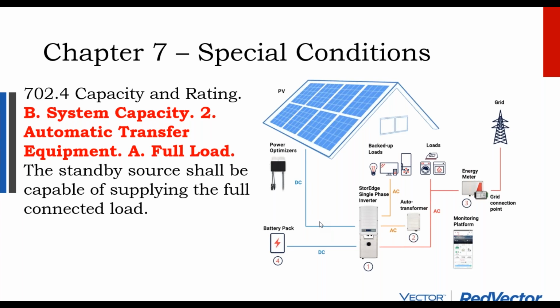Your systems would have to be very large and very expensive to get there, or you have to do very advanced and complicated load management to make sure that your load stays within the load of the backup power system. And so most battery inverters only back up a critical load panel rather than backing up the entire building, whether it be commercial or residential. Your battery inverters, they can be used for other things than just backup power. They can be used to kind of game your electric bill for cost savings.